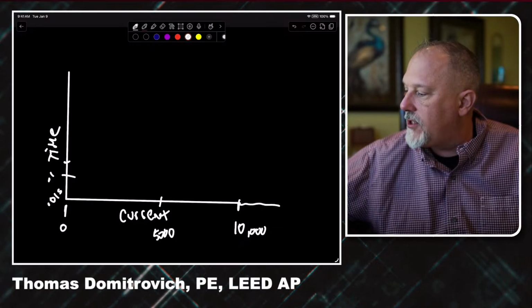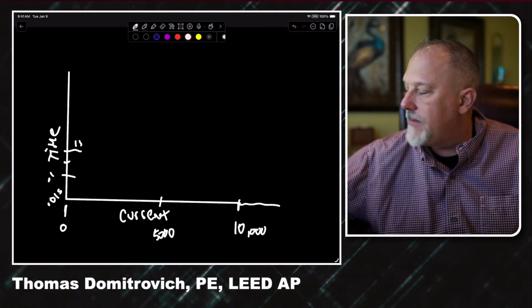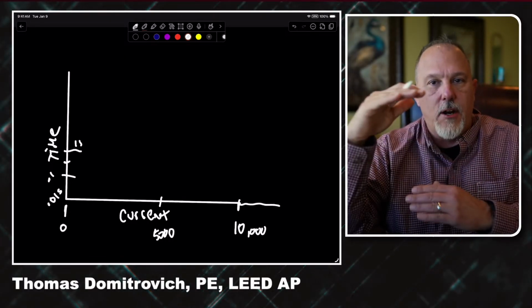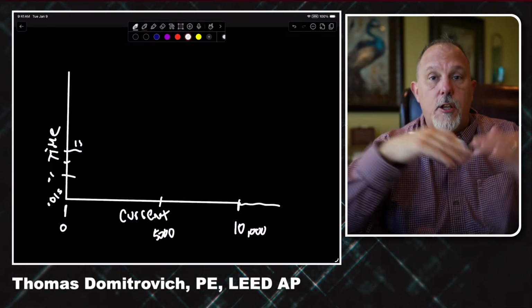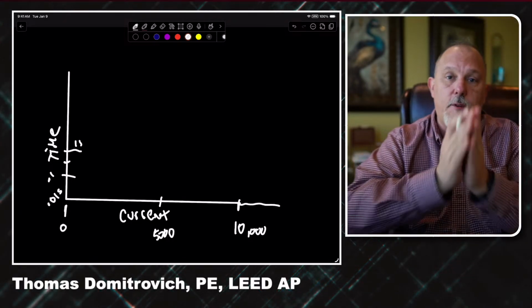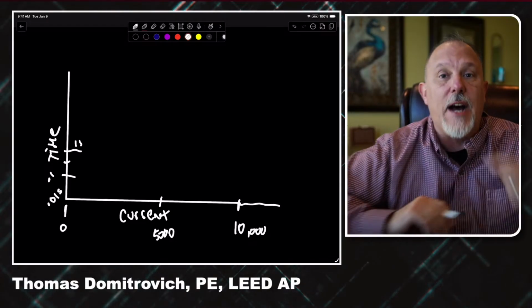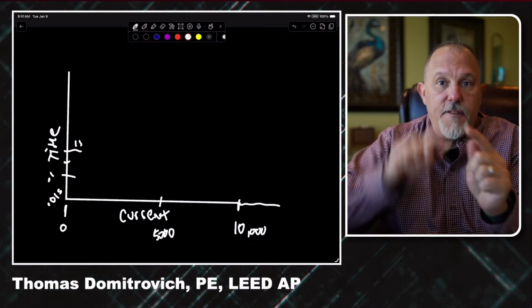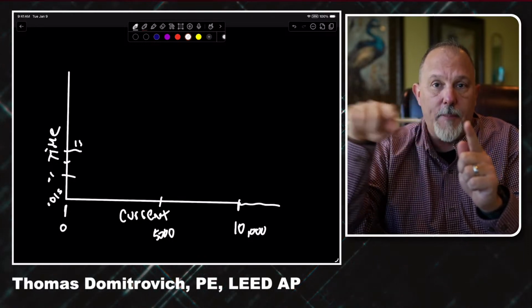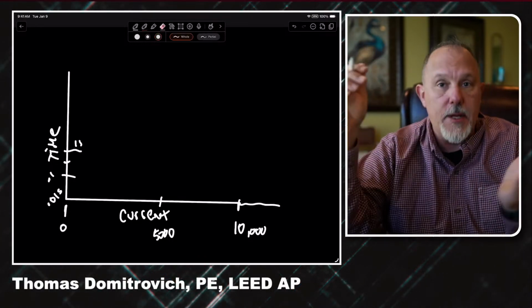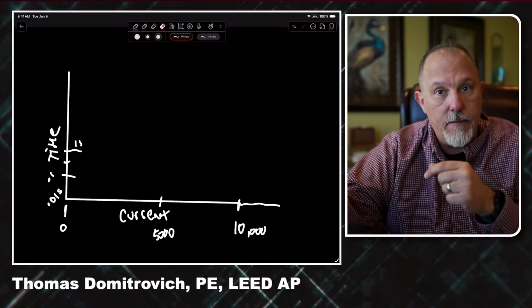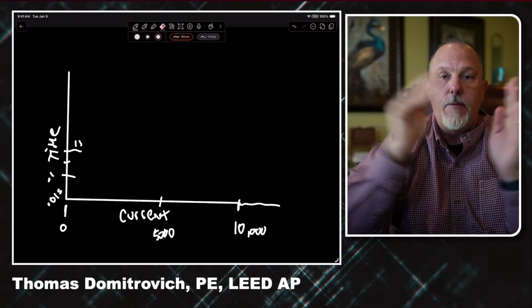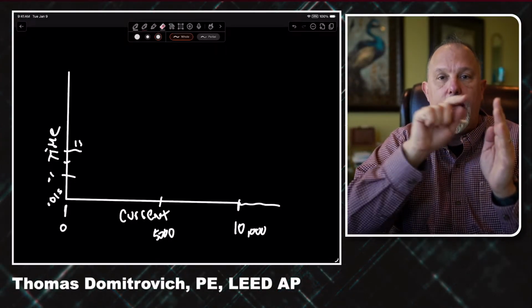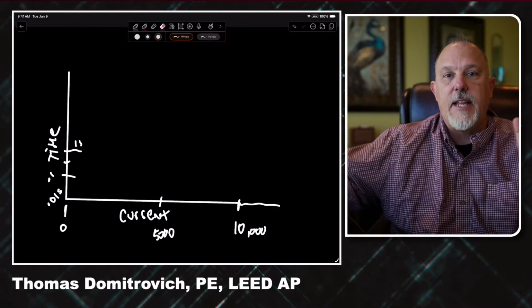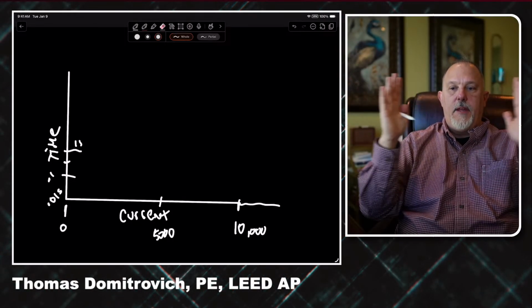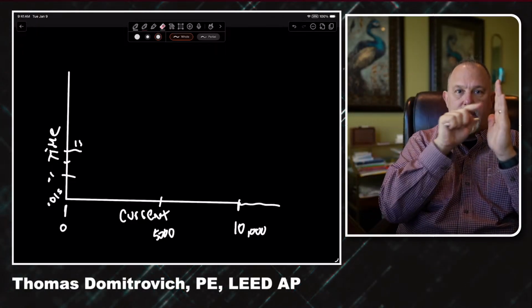Say 0.1, say that's 0.2, say this is 1 second, etc. So it's, again, log to log. And the reason they do log to log, logarithmic in the vertical axis, logarithmic in the horizontal axis, is because if I did equidistance for every segment, let's say I go up in increments of 1 second, of 1 amp, that paper would be about a mile long that way. So to shrink it up, they go logarithmic, so that I'm basically taking this line that would be huge, and I'm shrinking it down to get the same number in.